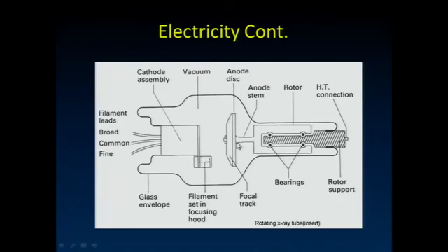And that's on the order of 100,000 volts. And that electron is now accelerated towards that anode and strikes it with a lot of energy. How much? Well, 100,000 electron volts, 100 keV when it strikes that. That's how much kinetic energy it has. That creates a lot of heat that ends up dissipated in this anode here. And so we really need to help dissipate that heat, and one thing we do is rotate the anode.